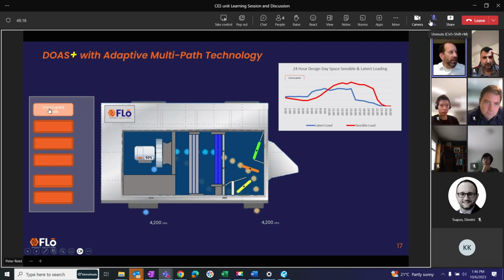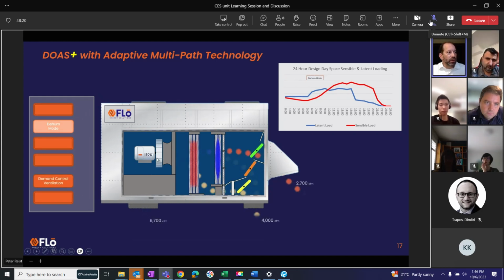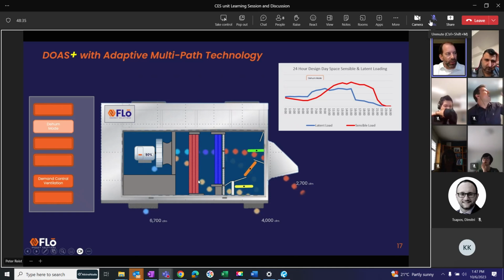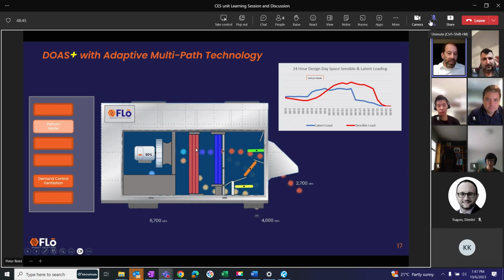But as soon as people come into the store, maybe the staff, maybe early shoppers, we have to have ventilation. And so our outside air damper opens, and now you get this inrush of hot, humid air, or not hot necessarily, but at least humid air from the outdoor. And this is when we go into the DOAS Plus configuration. We bypass our return air, we focus our coil on dehumidification, we take all the moisture out, and then we mix it afterwards. Now, this coil you'll see here, this is a reheat coil or a reclaim coil.